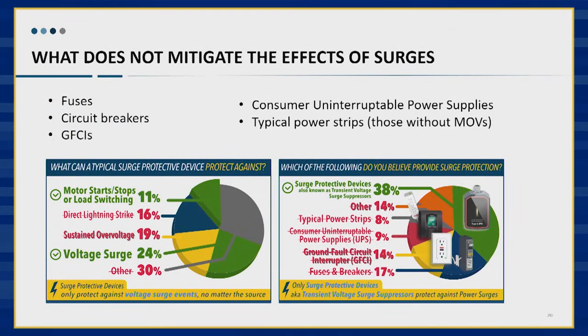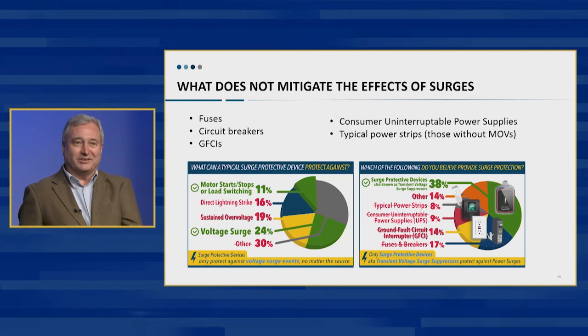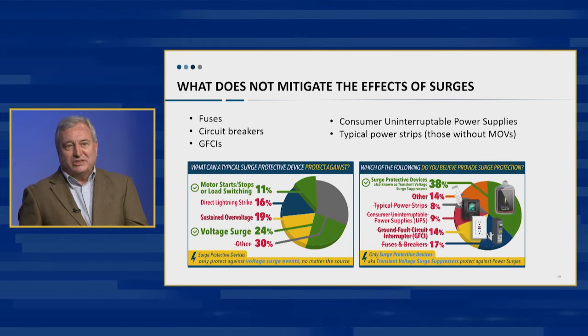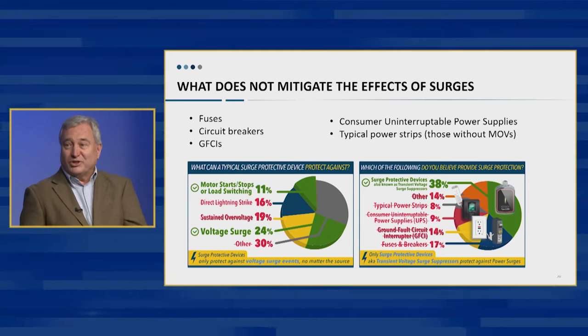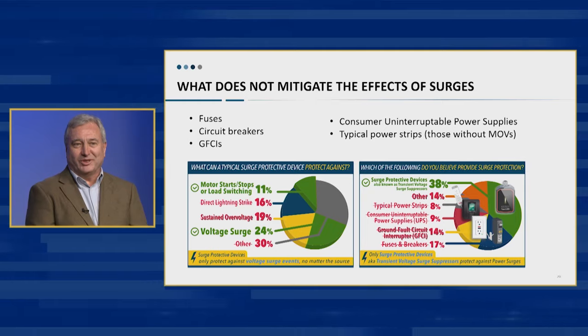Yeah, I mean, fuses and circuit breakers are for overloads and short circuit current protection. That's certainly not going to do anything when it comes to transients. Transients are going to blow right by them. If it's a big enough transient, we've seen cases where they might trip a breaker, but they're certainly not going to address transients. A GFCI is a ground fault circuit interrupter. That's right. Certainly not going to do anything for surge protection.